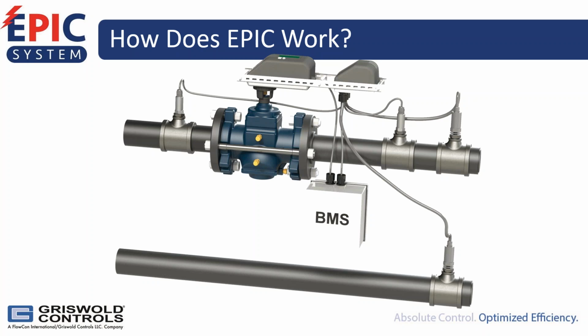So what happens when the system has a pressure change? Well, in delta T control product, if there's a pressure change, the system is waiting to read a change in delta T. But with our pressure independent valve incorporated into the EPIC system, if there is a pressure change, it maintains the same flow, so you get the same delta T across your heat transfer. So there's no need to modulate or cycle the valve to bring the delta T back in when there is a change in the system pressure.